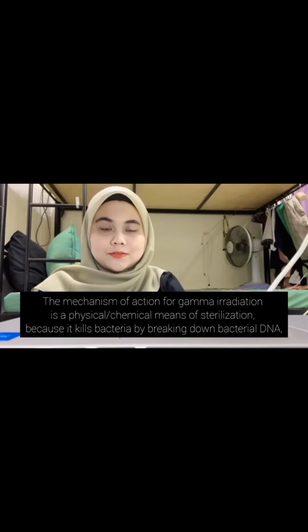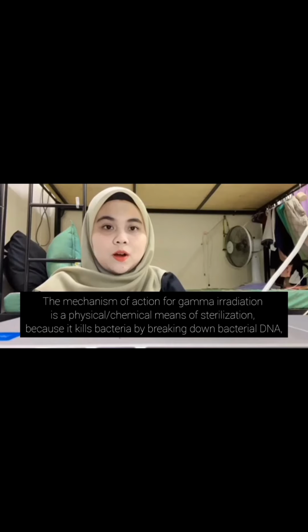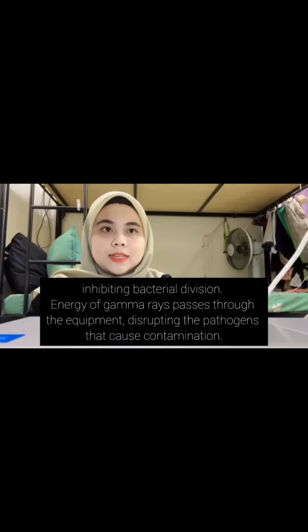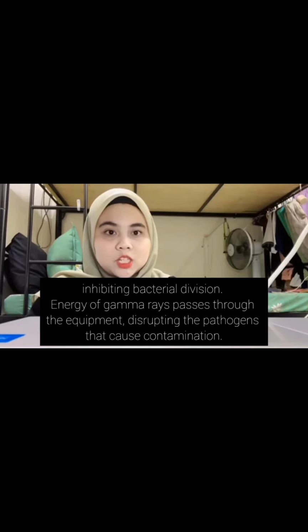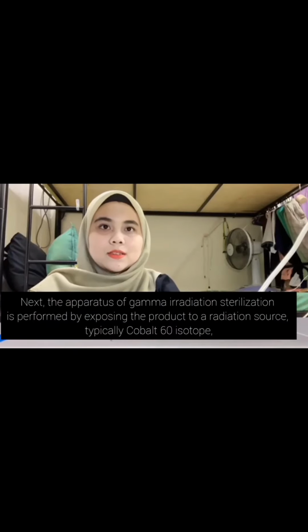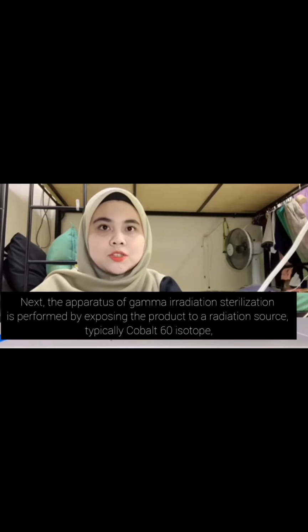The mechanism of action for gamma irradiation is a physical or chemical means of sterilization because it kills bacteria by breaking down bacterial DNA, inhibiting bacterial division. The energy of gamma rays passes through the equipment, disrupting the pathogens that can cause contamination. Next, the apparatus: gamma irradiation sterilization is performed by exposing the product to a radiation source, typically cobalt-60 isotope, which decomposes into nickel-60 isotope, firing gamma rays in the process.